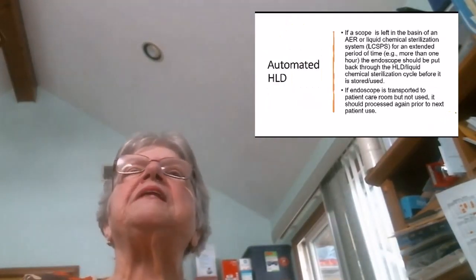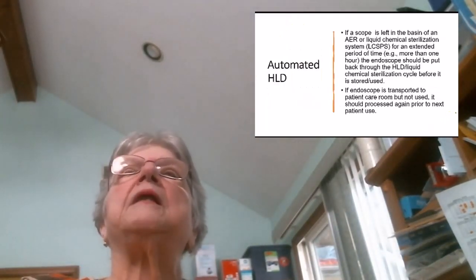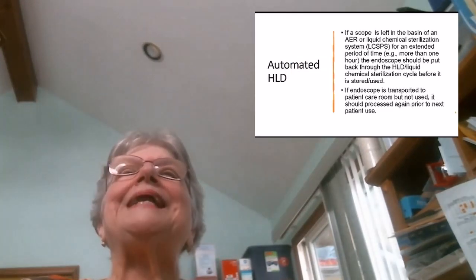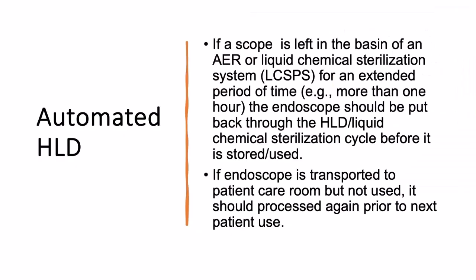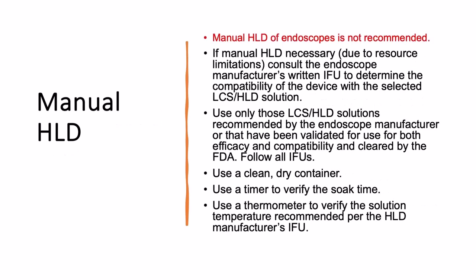If a scope is left in the basin of an AER or liquid chemical sterilant system for any extended period of time, about an hour, the scope should be put back through the process before it is stored or used. And if an endoscope is transported to a patient room but not used, it must be processed again prior to the next patient use. Now, we said manual high-level disinfection of endoscopes is not recommended.